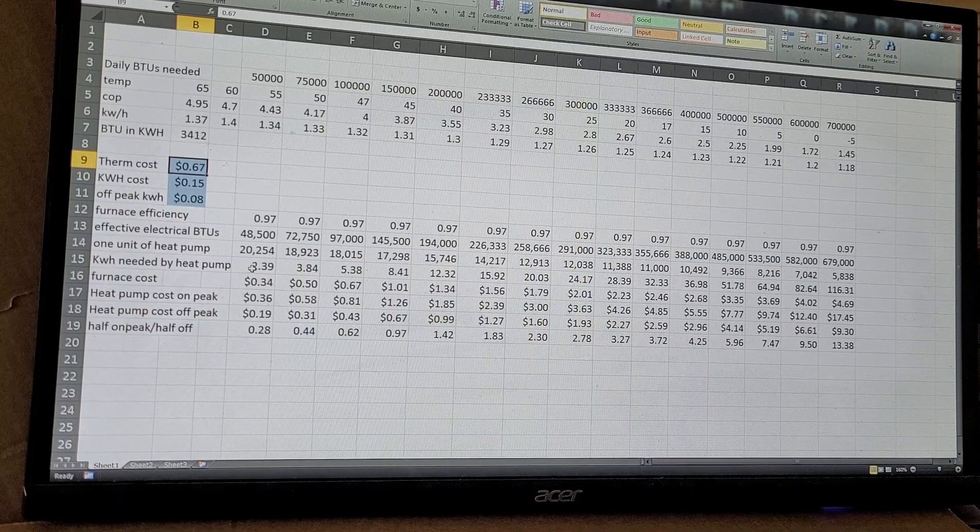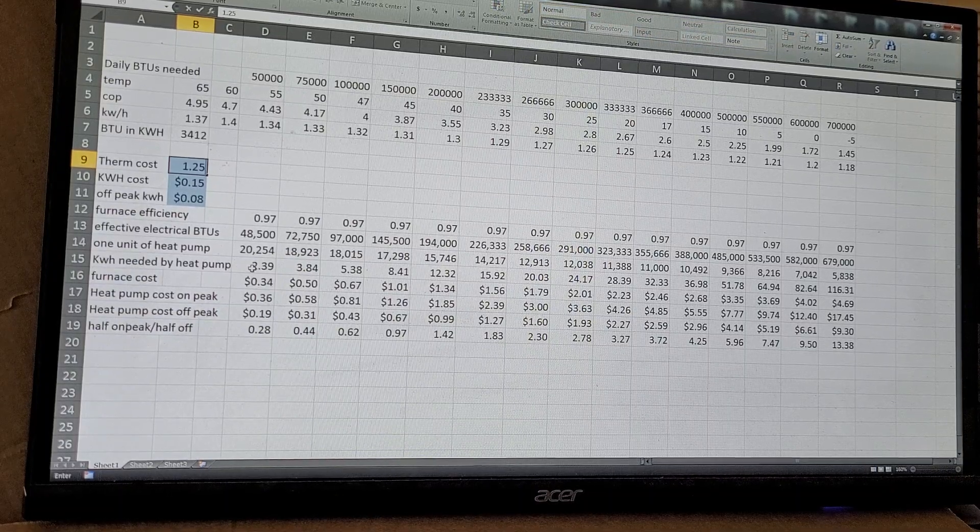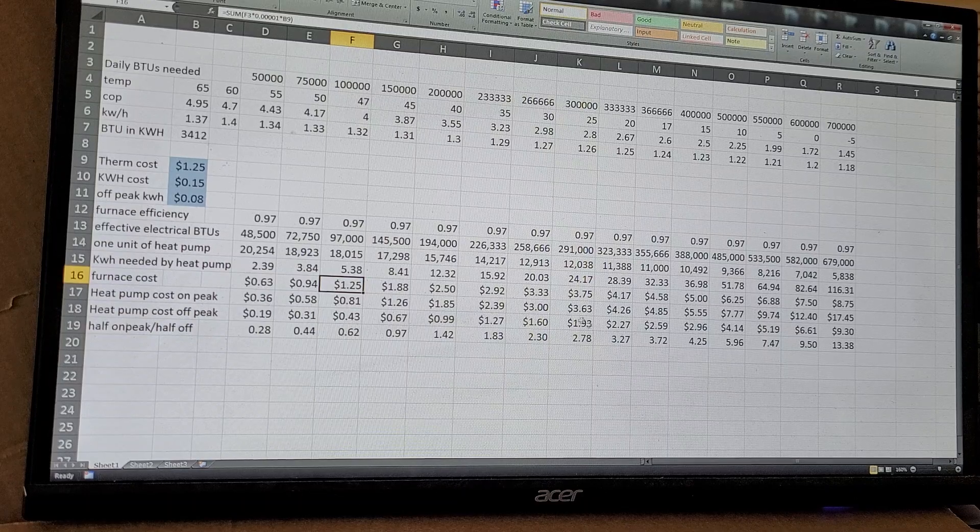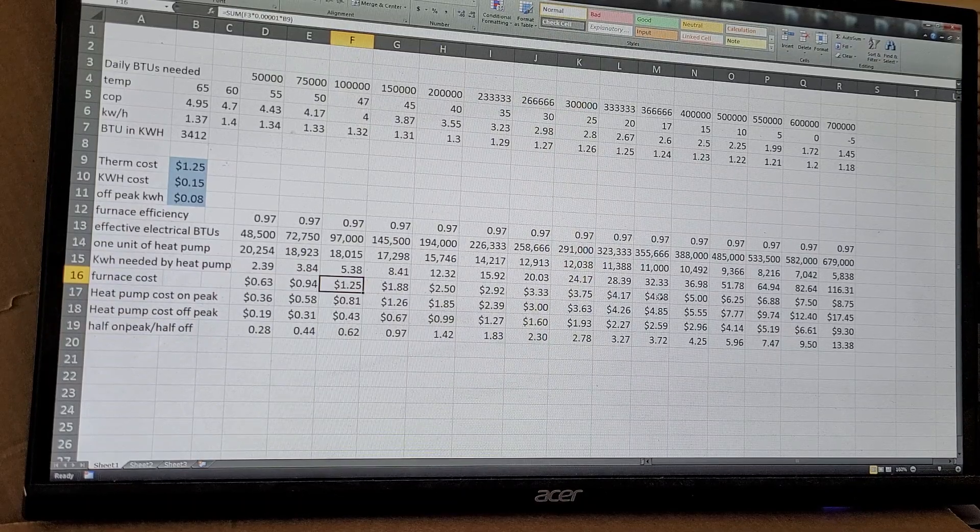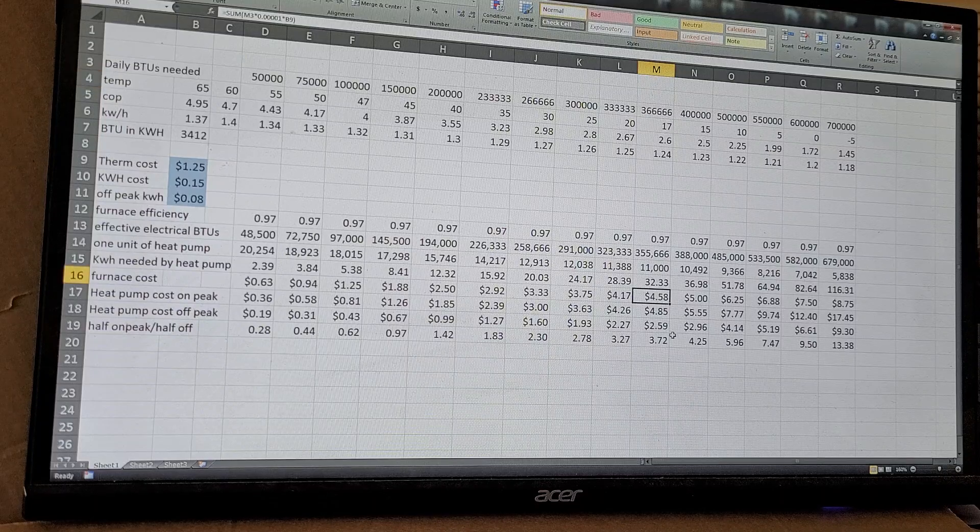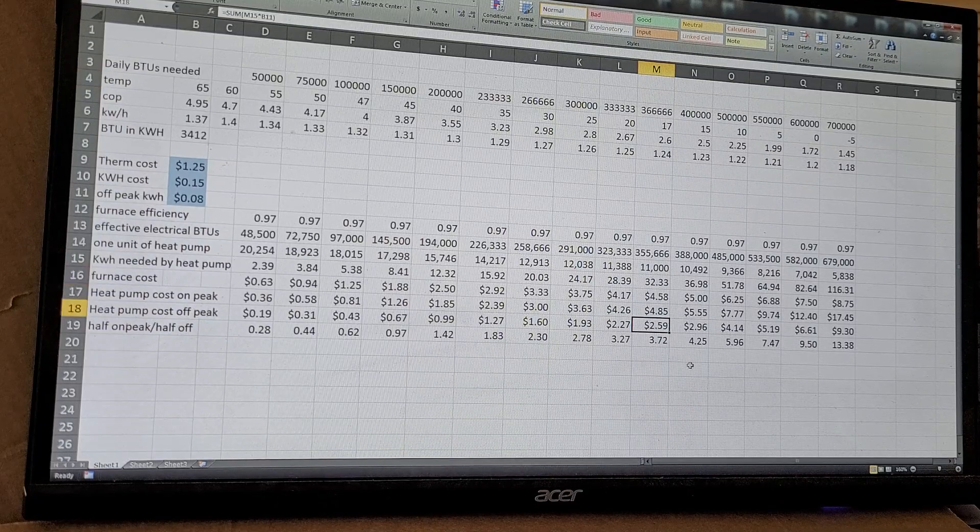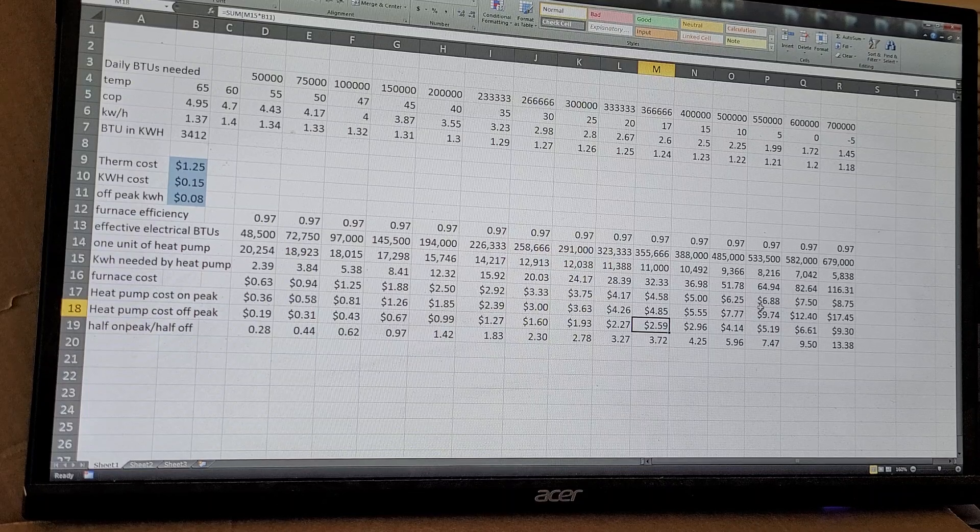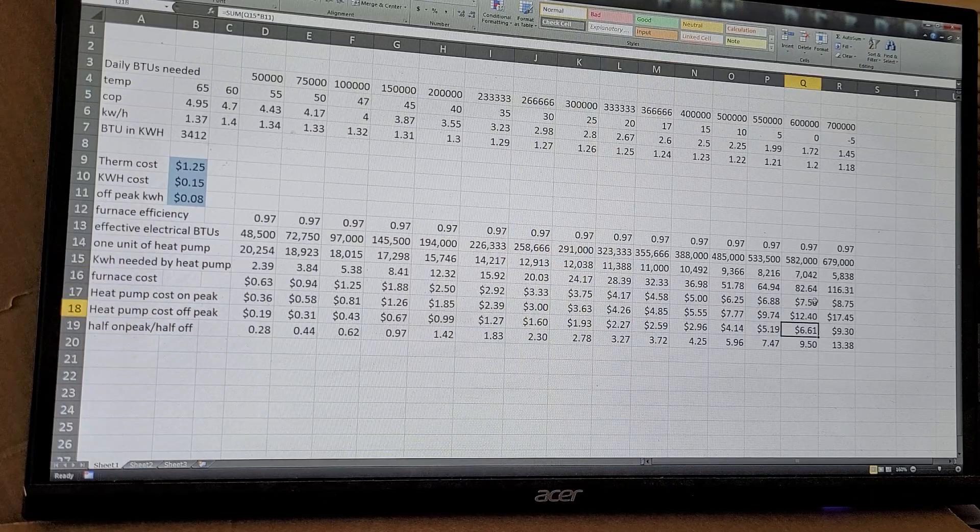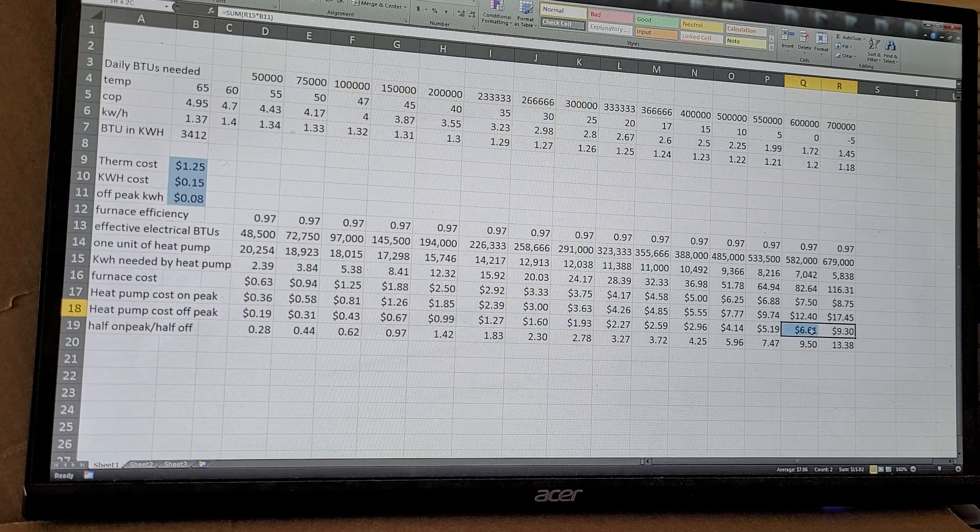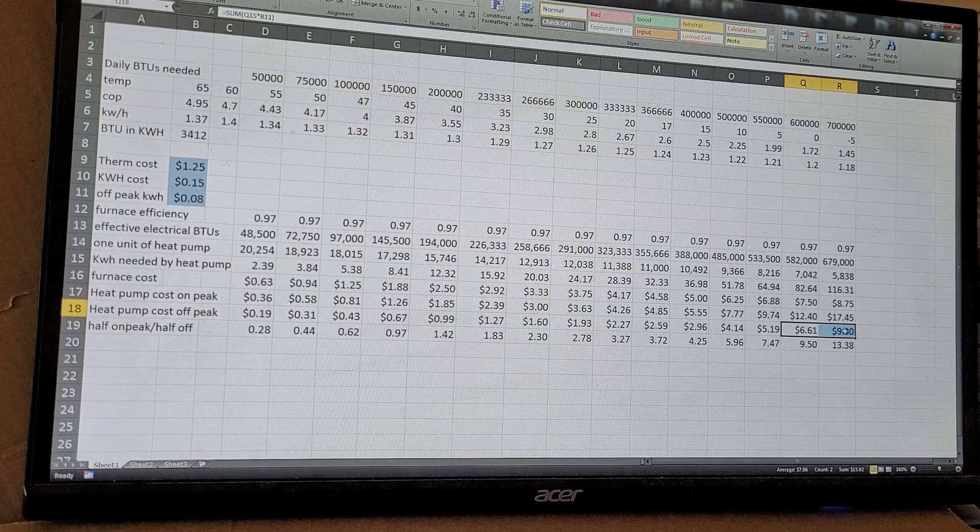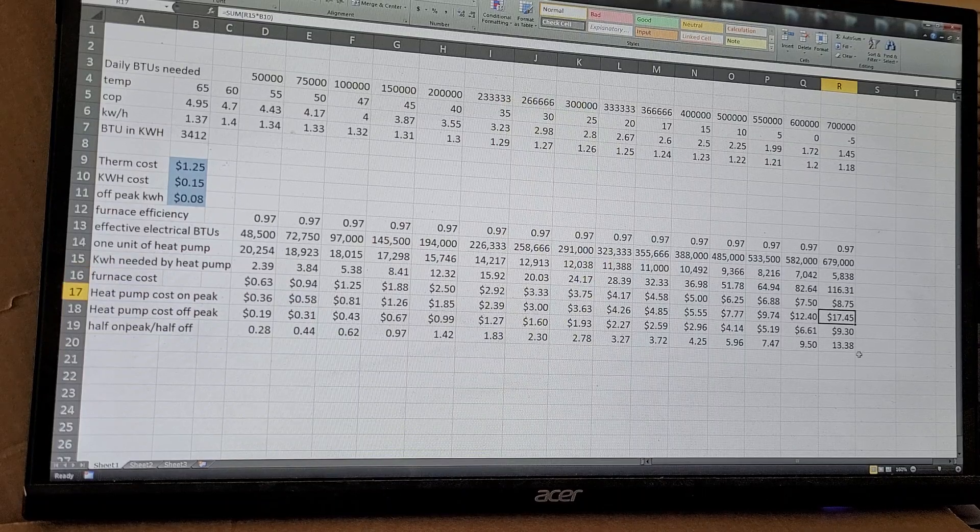A couple years ago when I was paying a buck twenty-five, you can see how the numbers start to change. Now the furnace at 17 degrees was costing four dollars fifty-eight a day to heat, but only two fifty-nine on the heat pump. But when it gets down to zero, you can see that the changeover is somewhere between zero and negative five where the heat pump actually costs more.